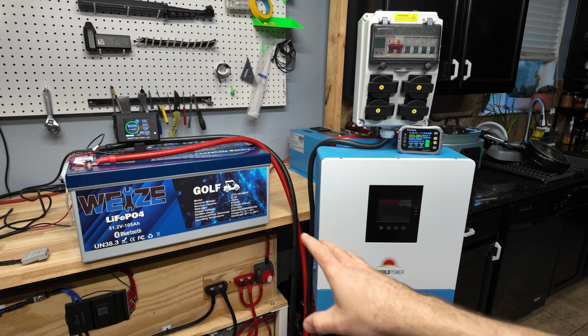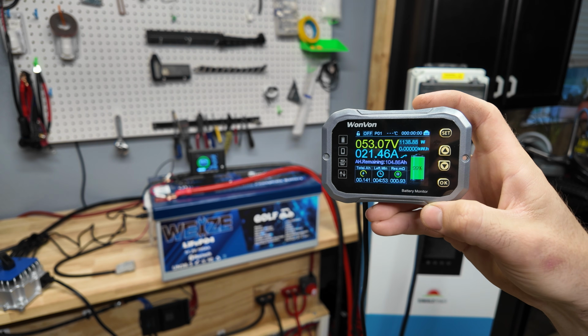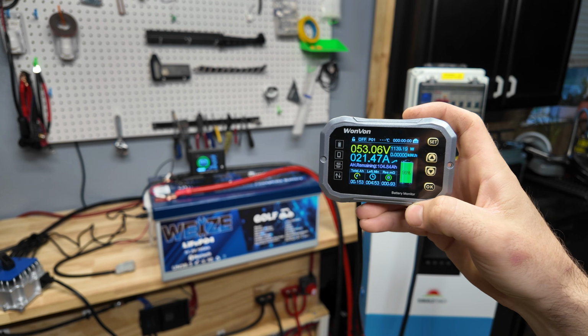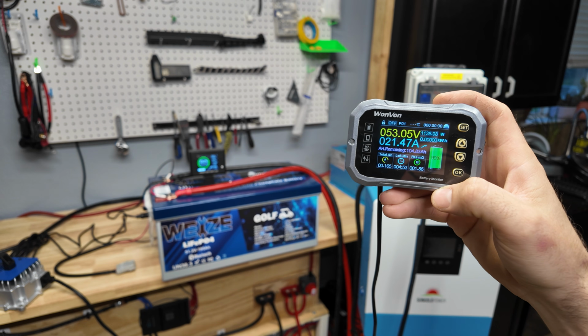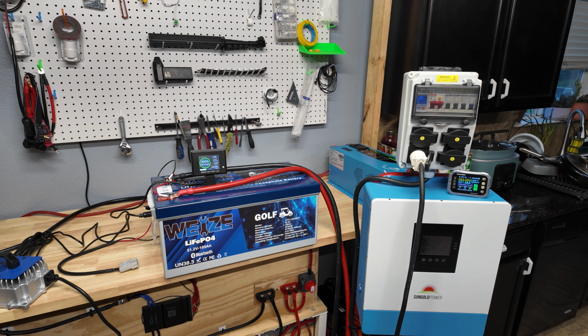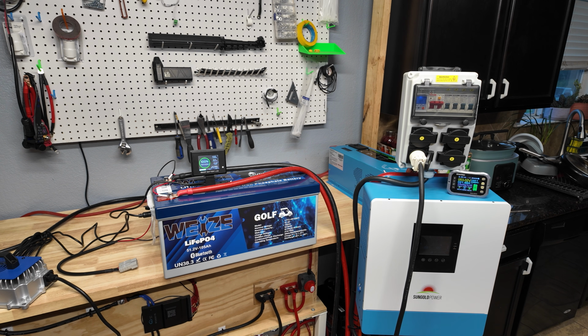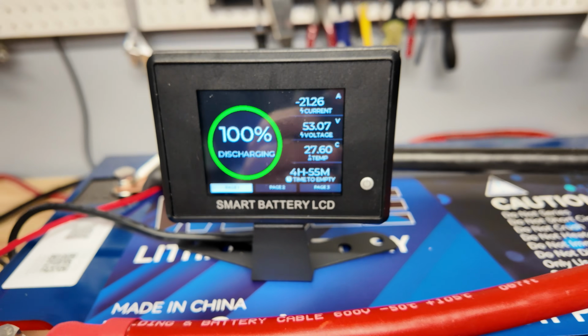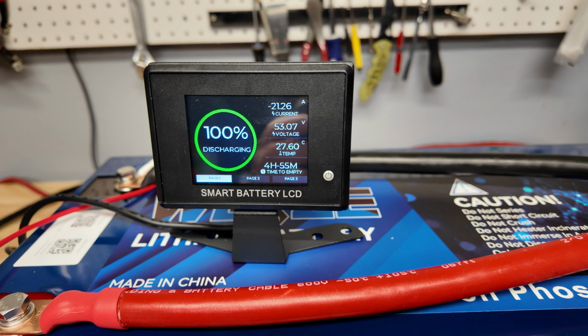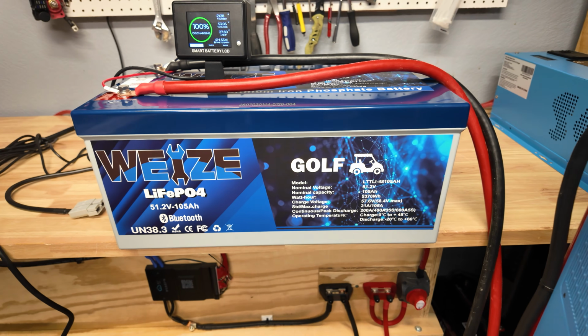The battery has been fully recharged, and we're pulling about 21.5 amps, just what the battery charger is going to use, so that's pretty close to 0.2C. We're just going to let the test run until the battery shuts down. The inverter's low voltage cutoff is set very low, so the battery should shut off first, as you can see from the battery meter reading. I'll see you guys back here in a few hours, we'll see what this thing can do.